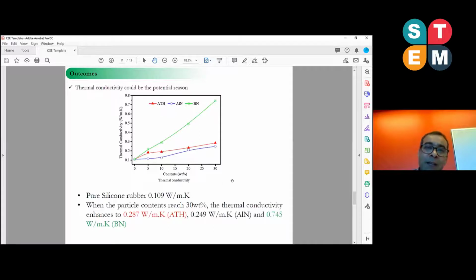So why is this happening? Why are the ATH and especially the BN, boron nitride, performing so well? The reason is that we experimentally measured the thermal conductivity of each sample. Thermal conductivity increases linearly with the addition, but with the BN, because BN is an inert, inorganic filler, it can increase the thermal conductivity of the insulation and at the same time retain good electrical insulation properties.